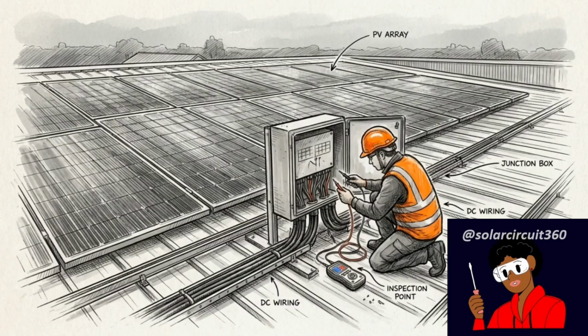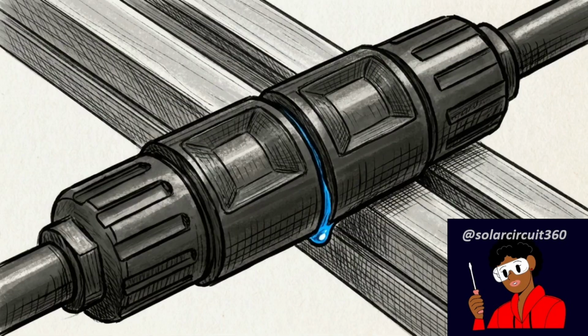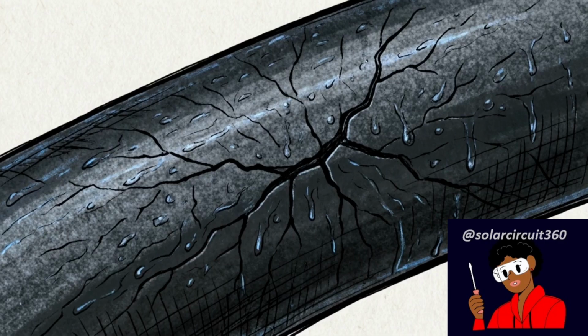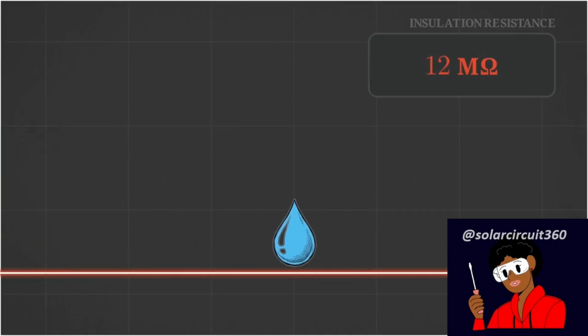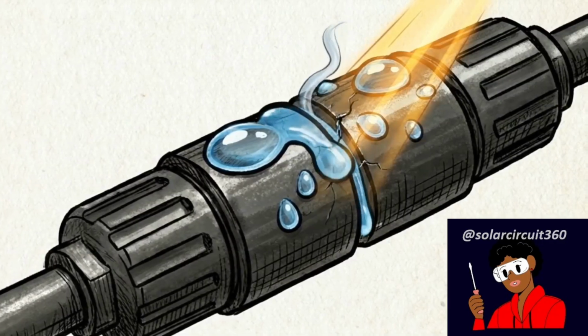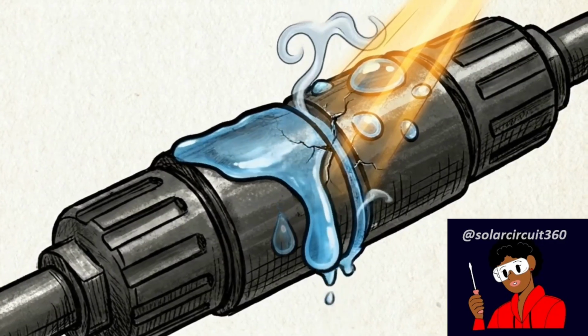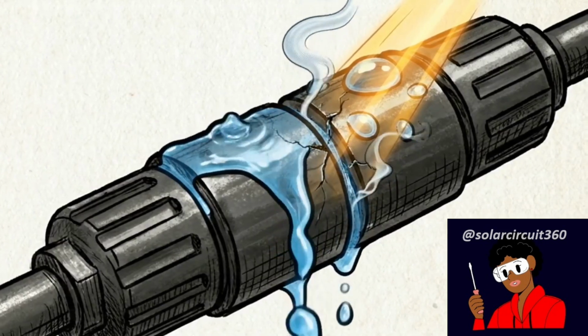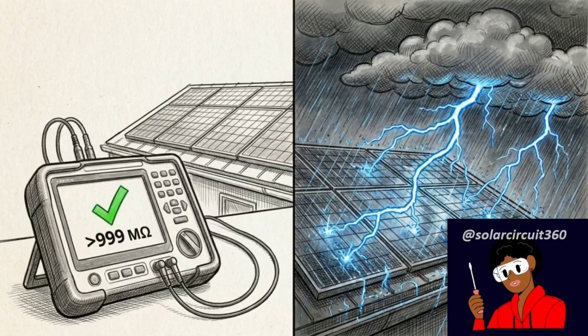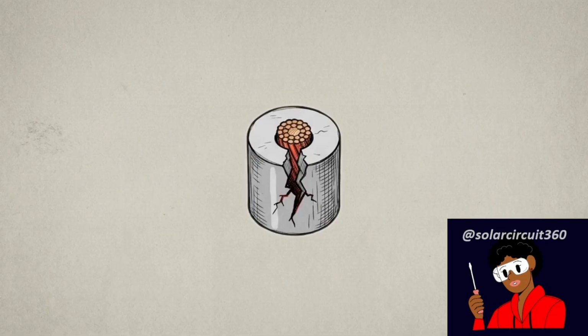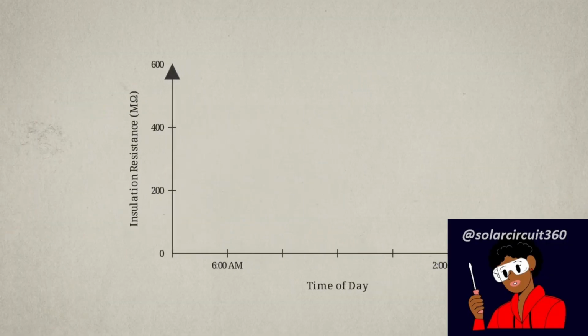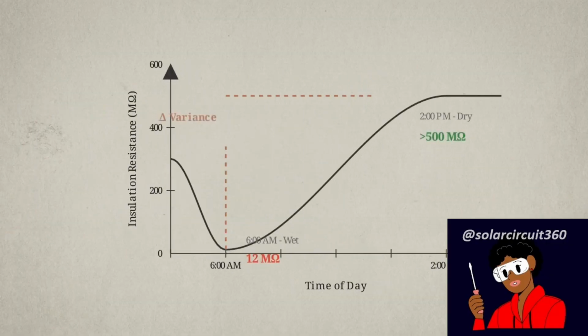One of the most difficult variables to account for in the field is intermittent water ingress, often found in poorly crimped MC4 connectors. Morning condensation can provide a conductive path across damaged insulation, causing a sharp temporary drop in resistance. As the rooftop heats up in direct sunlight, this moisture evaporates. The cable appears to recover high resistance, even though the physical defect remains. A cable that passes a test on a dry afternoon may still fail during the next rain cycle, potentially creating a hazardous leakage path. Identifying these transient faults requires comparing morning and afternoon readings to ensure the hardware is truly stable.